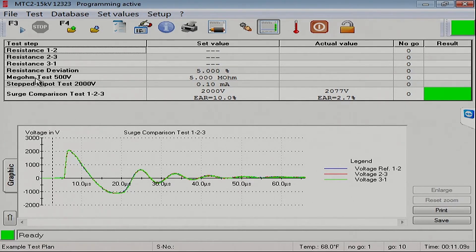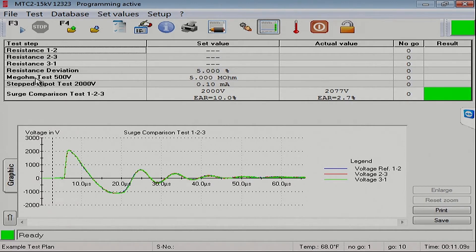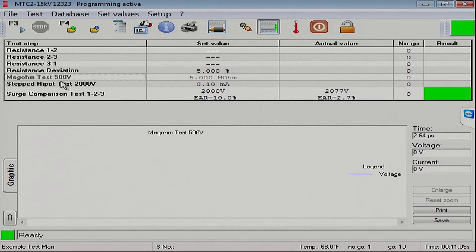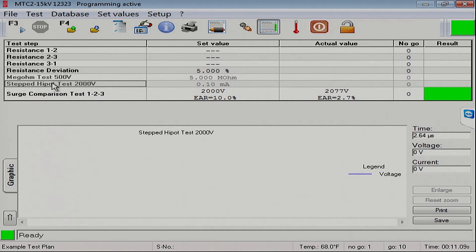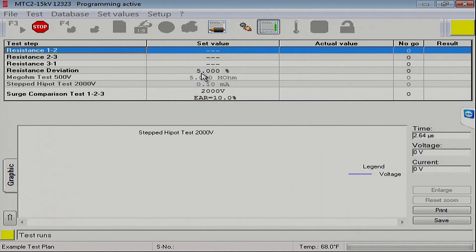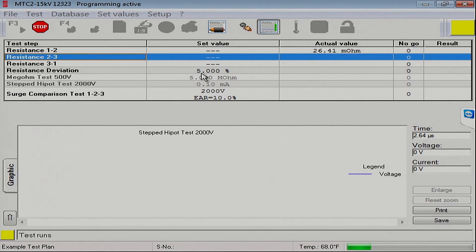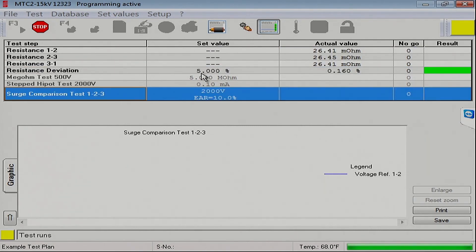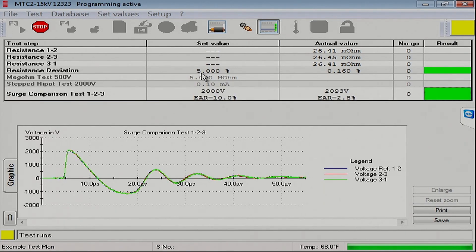Just to show you another feature of the MTC2, we can turn off individual test steps. Let's say we just have already done them or don't care to do that particular test. Right now, I'm going to turn off the megohm test and the stepped hipot test just to demonstrate this feature. And we can show you the full test running. I'm going to disable the megohm test, as you see there. Notice it turned gray. Now, I'm going to disable the stepped test. And you can see it also turned gray. I'm going to save those changes and run the test. I will test without order. I'll cover that test without order in the work order scheme in another video.